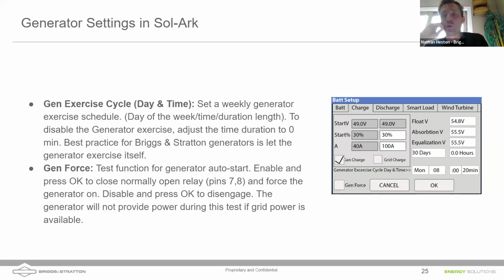No, in fact, the gen port, as long as you've not told it to use it as a smart load port, will not be active at the same time as the grid port. So it can exercise the generator. It would not cause an error if you have that exercise when grid is still active. So great question. Answer is it won't cause a problem. Yeah, and I would say also, if there is a transfer switch, my understanding is that it doesn't transfer during those as well. Yes, exactly. It will not start using the generator power. So additionally, Daniel, you're going to point out here that you can do a force gen. Yeah. That'll force that generator to start up. But in a grid-up situation, it still won't be using that power. Great. I think you addressed it, Nathan. Let's keep going.